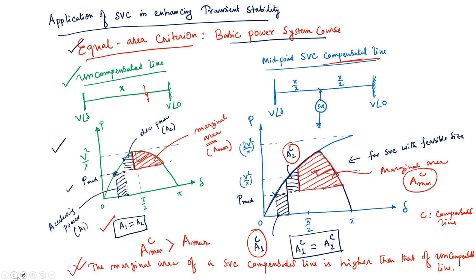If you recall from the last lecture, I discussed the equal area criteria for an uncompensated line and also for a midpoint SVC compensated line. For the uncompensated line, this is the P-delta curve, where P means power transfer and delta is the angular difference of the sending end bus and receiving end bus. Depending upon the loading of this line, the value of delta will change.